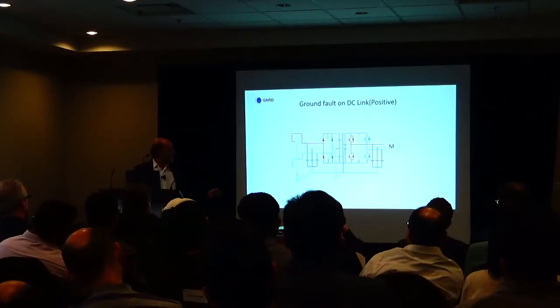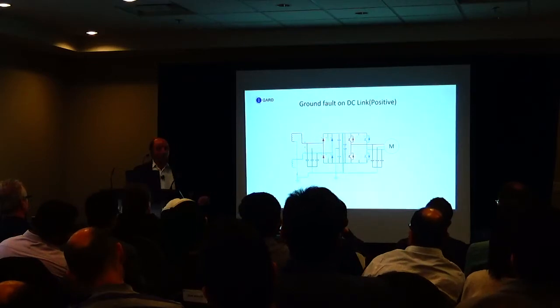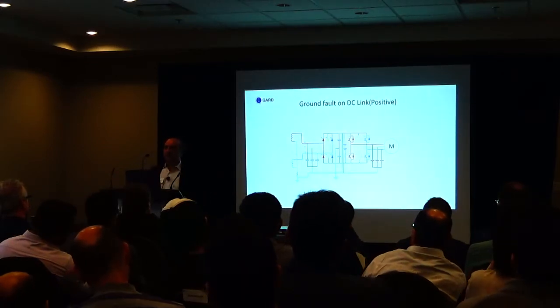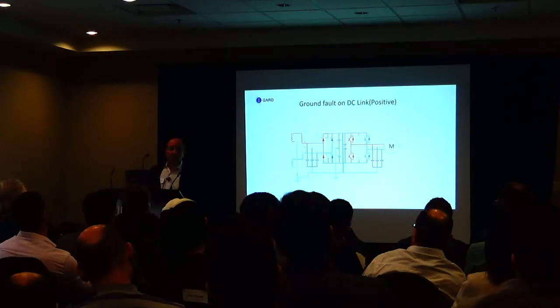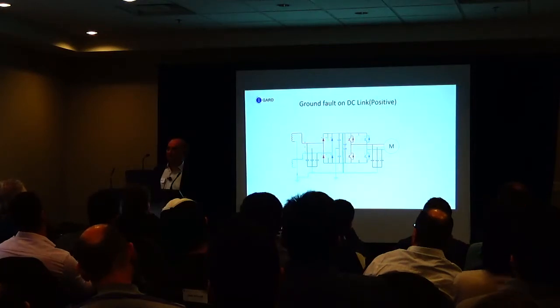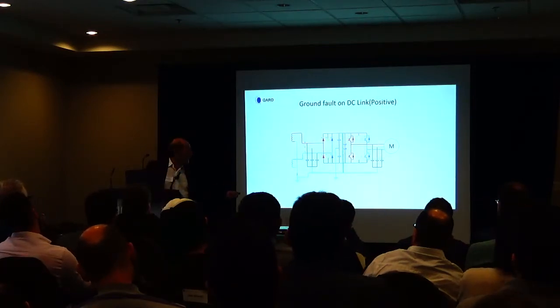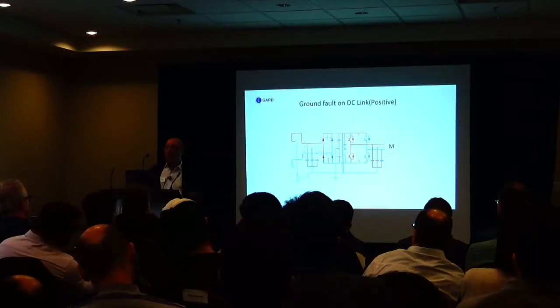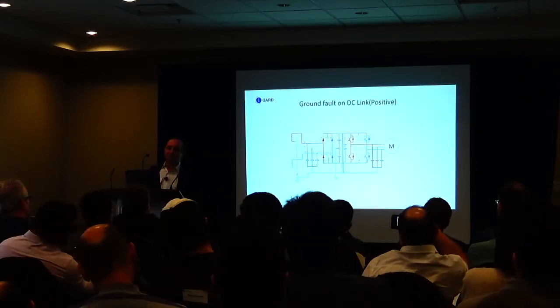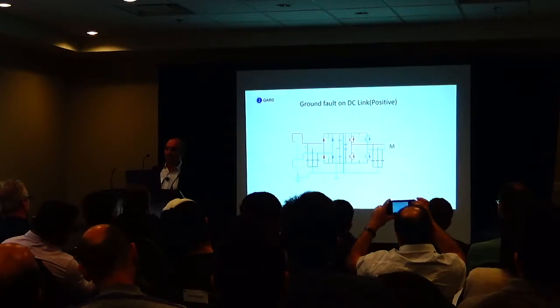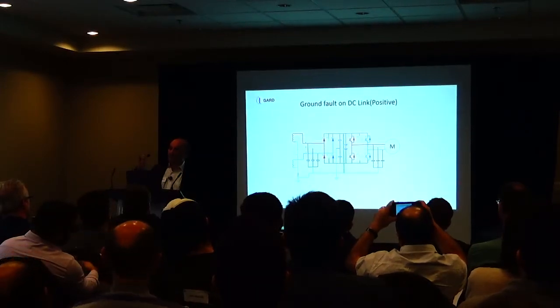So when it's filtered, it looks like this. So when you have a fault on the DC bus, where does the current go when you have a ground fault? We discussed this earlier. Back to the source. How does it go back to the source? You have a source that goes right back here. So what are we doing? We're impressing DC voltage across that resistor. But all 3 phases see that fault.